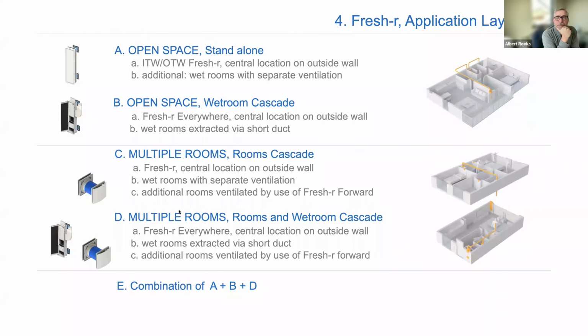It's very easy if we go into a single space and just install one, and it operates. That's scenario A, open space, standalone. It's pulling exhaust air in and giving fresh air out, all running on demand control, and everything's good. The next thing would be B, open space, wet room cascade. Essentially, we put it in the living room and run a couple of ducts back to the bathroom. So it's always pulling from the bathroom and giving fresh air to the living room.